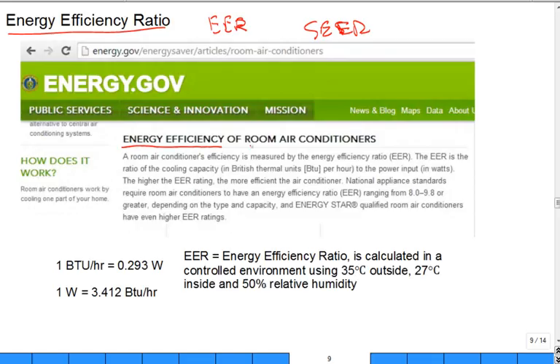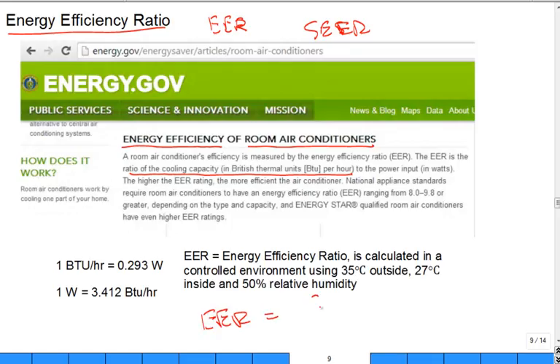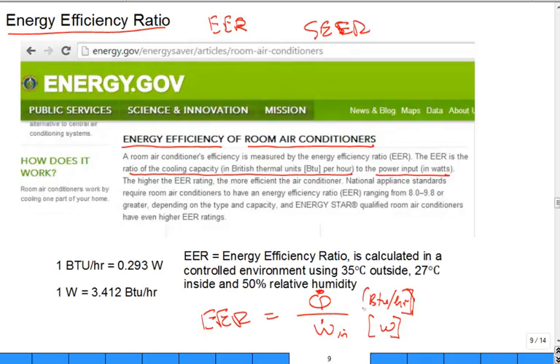The EER is primarily focused on room air conditioners, window units, and it's defined as the cooling capacity in BTUs per hour. So the EER is the rate of cooling divided by the power input in watts, W-dot input. This is in watts, this is in BTUs per hour. Is one BTU per hour equal to one watt? No. So you end up with this apparently dimensionless ratio, but it has units because they don't cancel.